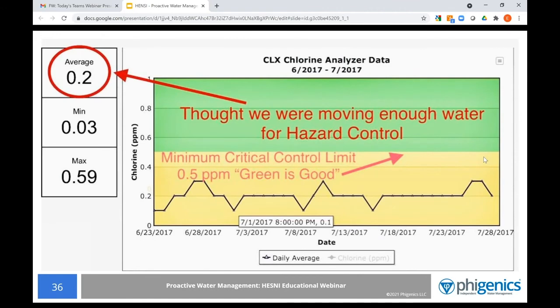So this graph shows the before situation. You can see that the team decided to set a control limit of 0.5 ppm as a minimum. The blue line you see at the bottom of the chart represents the daily free chlorine averages. You can see that it varies anywhere between 0.1 to 0.3. And if we look at our maximum value, sometimes those instantaneous readings were up near 0.59, and maybe at times they were achieving that control limit. But overall, the limit was not being maintained consistently.